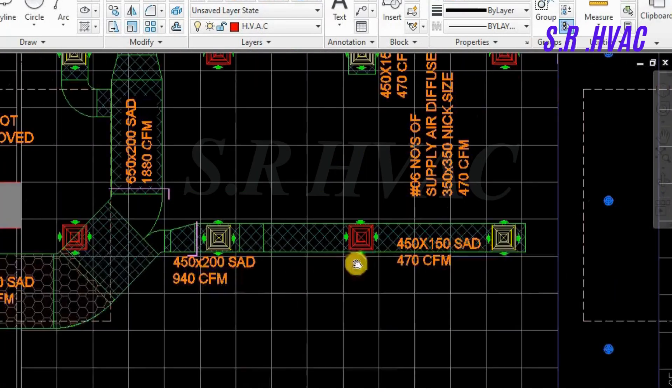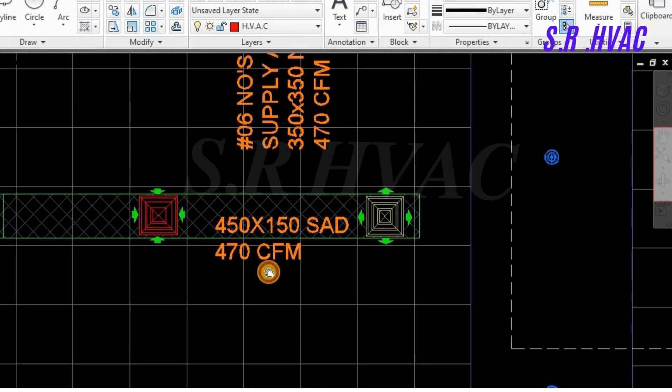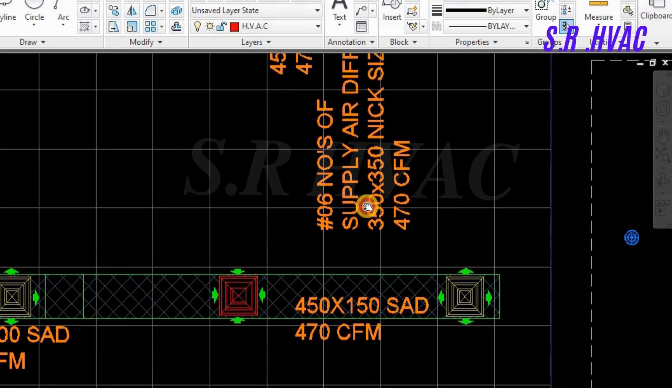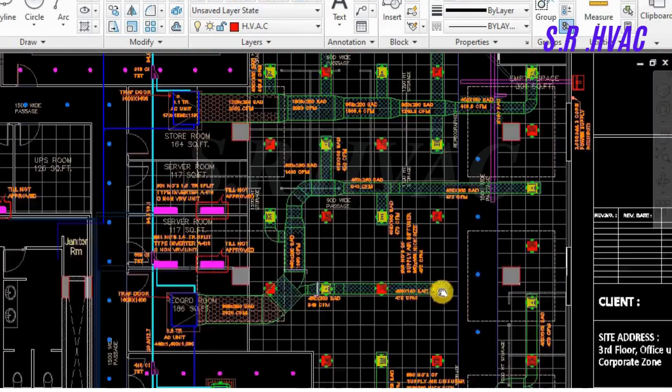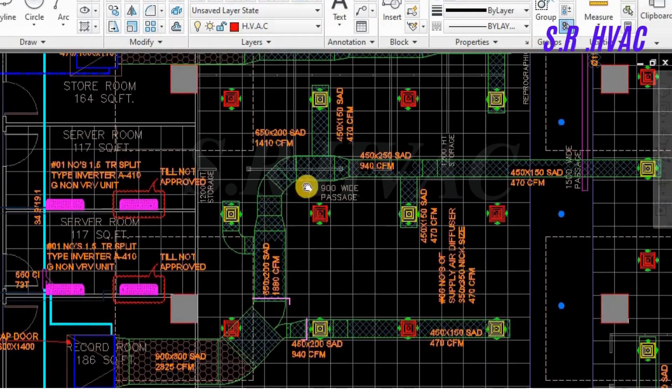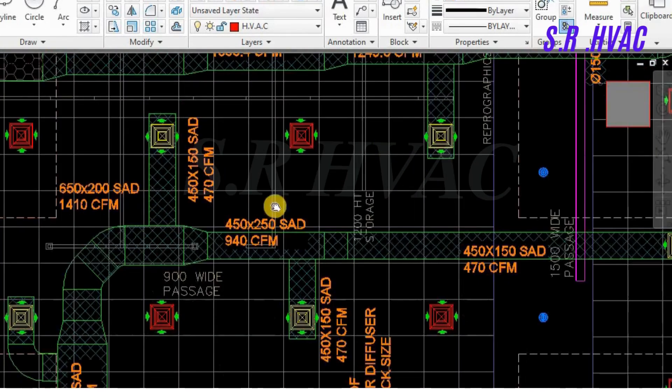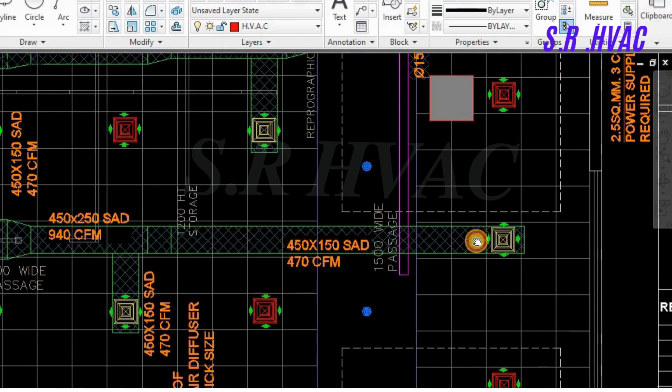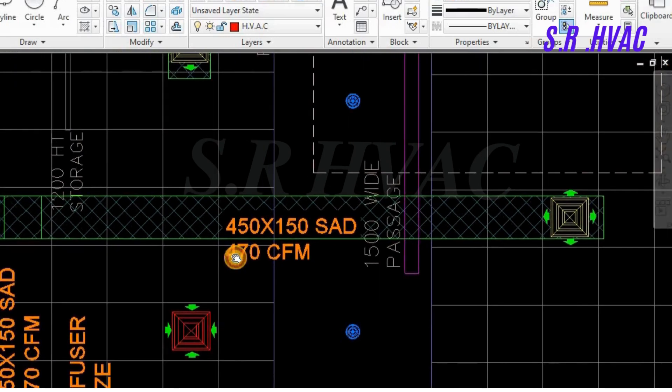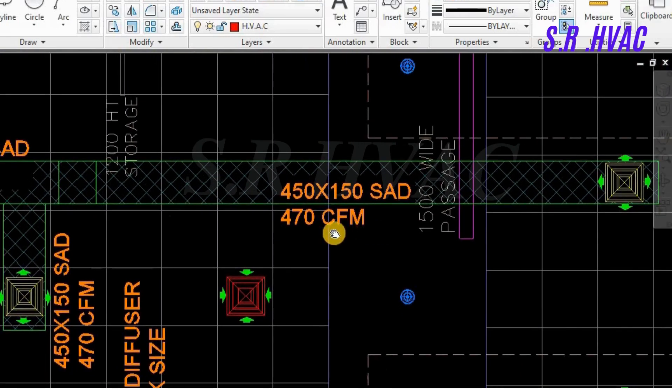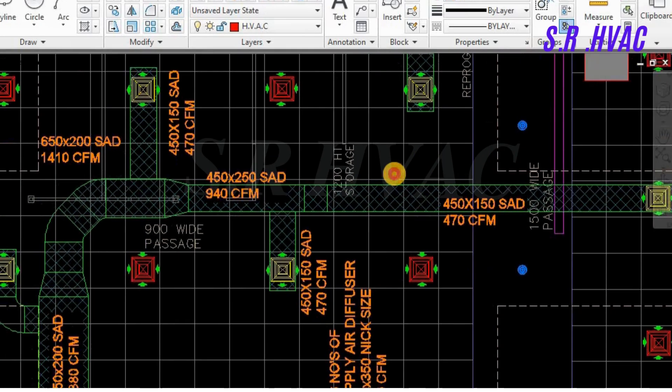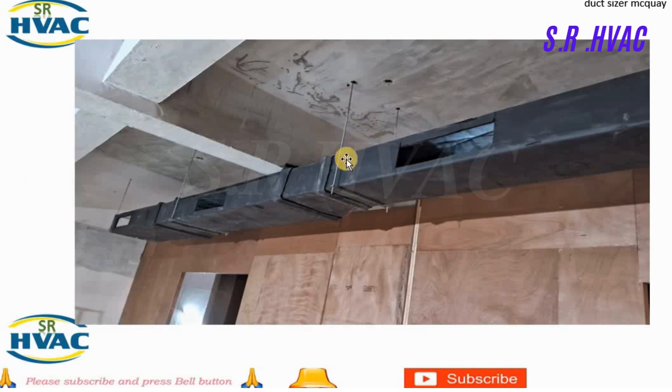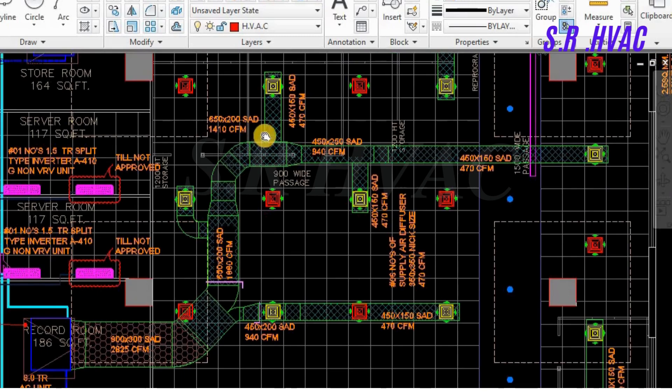So you can see this is the supply air duct, this is 470 CFM, the duct size is 450 into 150, supply air duct. There are six numbers of supply air diffuser. This is in the ducting, six supply air diffuser is taken. You can see as the duct goes, the air is flown out and the duct size is reduced. The last point is this one. The duct size is 450 into 150, this is supply air duct and this is 470 CFM, cubic feet per minute. This duct is hanged with the help of our C channel and threaded rod. I will show you one duct also. You can see the duct, this is covered with the thermal insulation. It is hanged with the help of threaded rod and C channel.